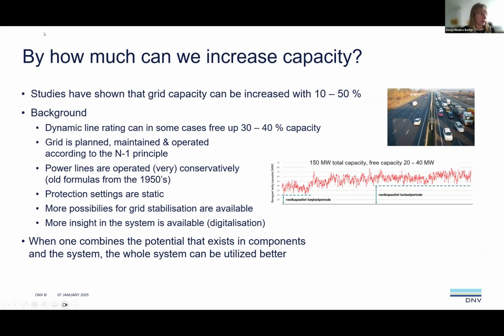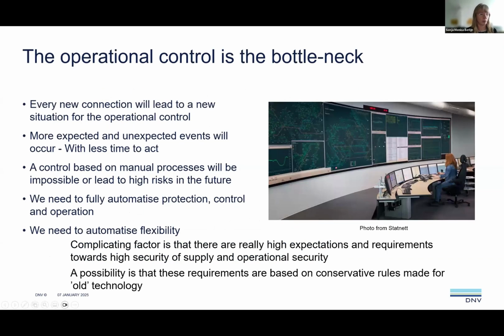So then another thing is that the security settings in a grid are very static. And we need more dynamic protection settings. There are some studies going on. And of course, we need to have much more insight in the system. And when we combine this potential that exists in the components of the system, the whole system can actually be utilized much, much better. So what is actually the bottleneck of all these technical possibilities? It is actually the control center.